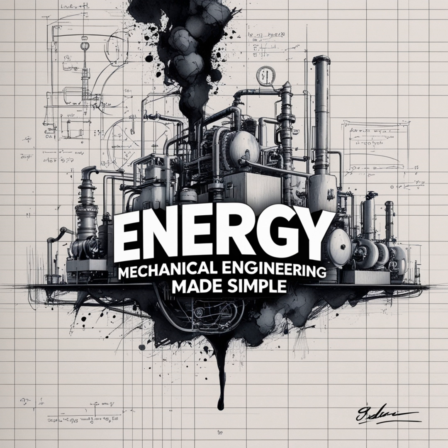That explains the big push towards variable speed drives, VSDs, doesn't it? Instead of the old way. Absolutely. The old way was often throttling. You'd install a pump sized for the maximum possible demand, and when you needed less flow, you just close the valve partway. Which just wastes energy, right? Forcing the pump to work hard against an artificial restriction. Exactly. It's like driving your car with the accelerator pushed down and controlling speed with the brake. Hugely inefficient. VSDs instead just slow the pump or fan down electronically.